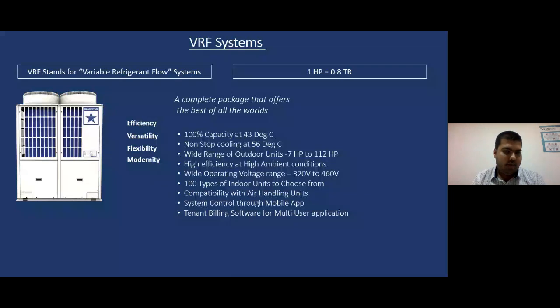So it's a huge range of outdoor units in VRF. It starts from 7 HP up to 112 HP single circuit, and it gives high efficiency at high ambient conditions. And as I said, there is a voltage fluctuation problem in India as well, so we are designed to cater to a high voltage range from 320 volts to 460 volts. There are a lot of indoor units to choose from, and it is compatible with AHUs, air handling units, as well. It can be controlled through a mobile app, and in case of multiple tenants, we have software which gives a multi-user application.